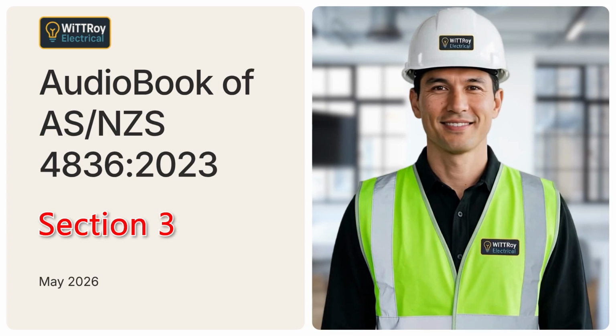After testing the circuit, the tester must be tested again on a known live source to confirm that it is still working correctly. This final test is very important. If the tester shows 0 voltage on the circuit, but the tester has failed, the worker may wrongly believe the circuit is safe. So the simple practical rule is this: test the tester, test the circuit, test the tester again. Only competent persons must carry out these tests. This clause also warns about testers that detect the electric field around an energized conductor. These testers are not suitable in all situations. They may not be suitable for screened cables, DC cables, or similar circumstances. DC means direct current. So when proving de-energization, the correct test equipment must be selected for the actual situation.